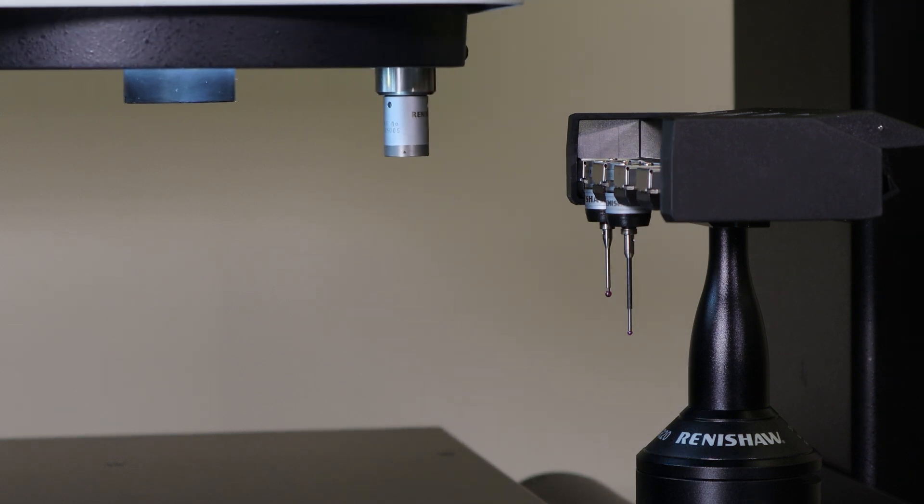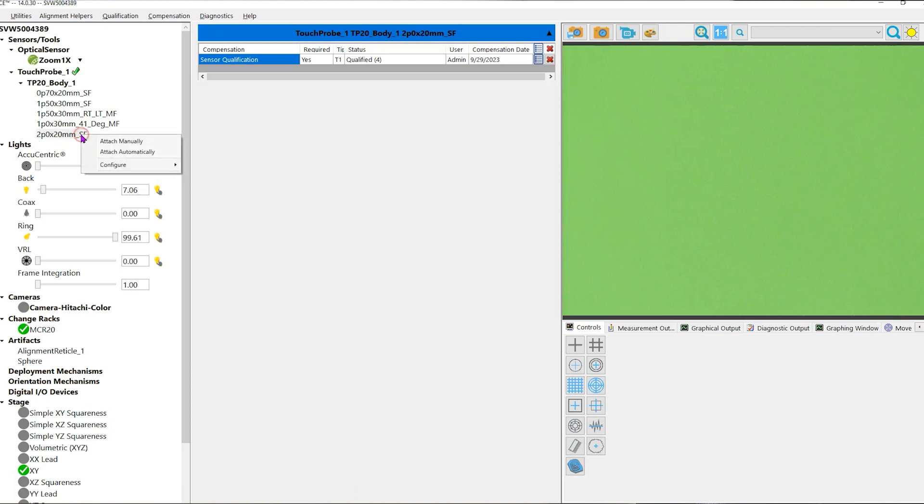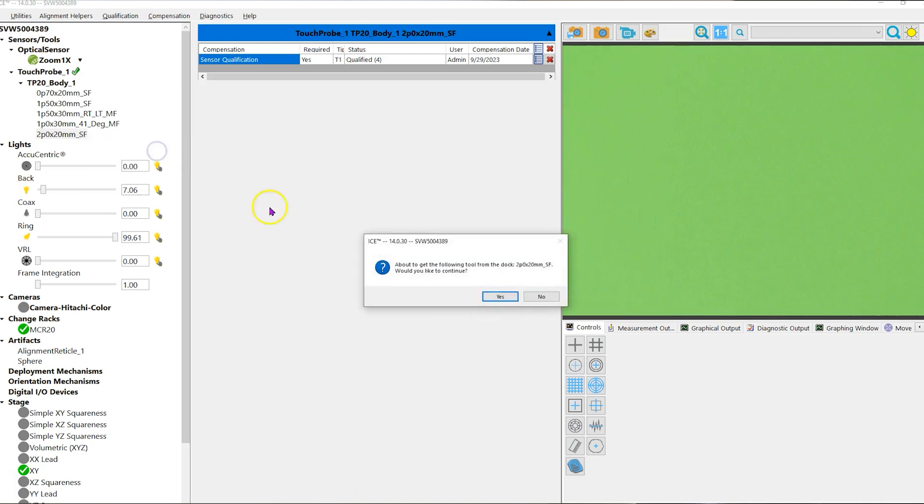To load the probe back into the machine, left mouse click on the probe name. Right mouse click and choose attach automatically at the pop-up window. A window appears letting you know the machine will pick up the probe.